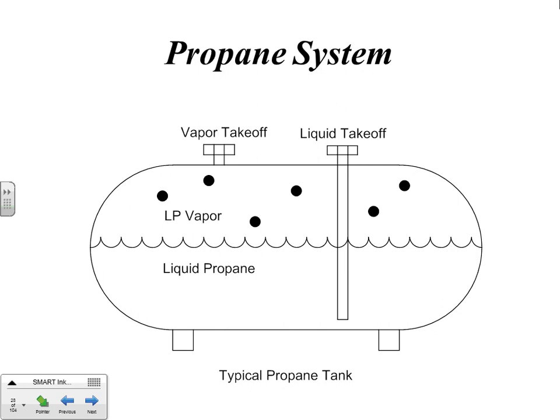Well, right there. Looking at this, typically in warmer climates, you would only be using a vapor takeoff. And because this liquid is under pressure, there's a lot of pressure in the vapor here. It's got natural pressure. So you open that valve, that gas is going to come out of there. In cold weather climates like we have here and in North Dakota, we've seen it along the I-90 corridor a lot. On extremely cold days in wind, it gets hard for a generator set to run because this tank cannot vaporize enough fuel to run the generator set.